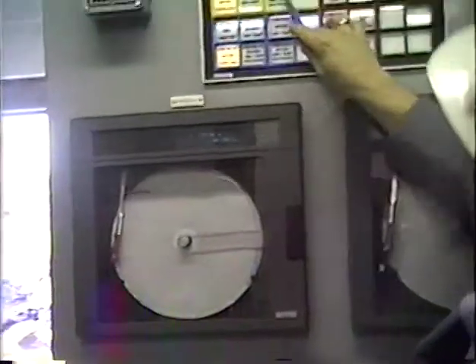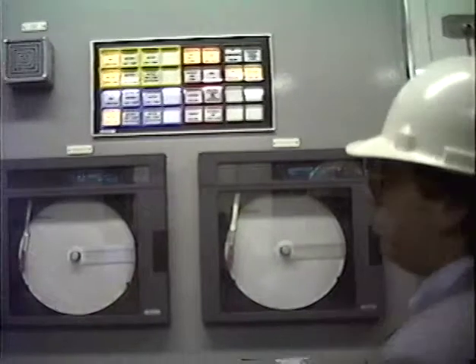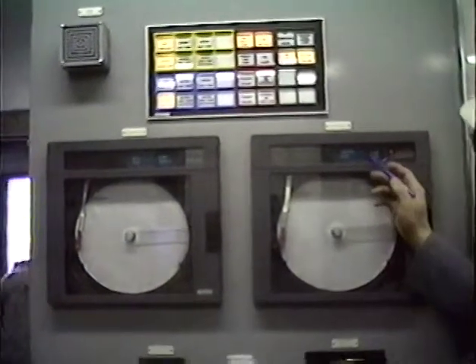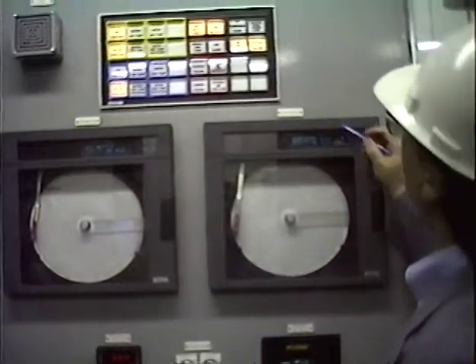the yellow is designated for fan one. The blue is down into red for the Baghouse and pre-coat. Green for some auxiliaries. As you can see, we've got compressed air, low pressure. And here we've got compressed air pressure channel 2 at 66 pounds, and we have an alarm, which is why we have that alarm. We have that because the compressor, for some reason, is probably shut down. We get up to 124, that would go out.